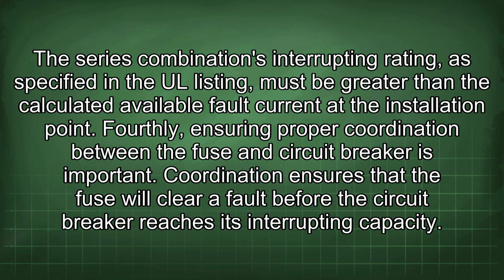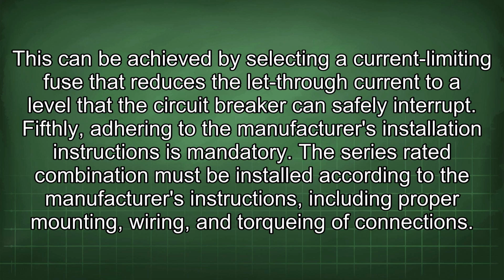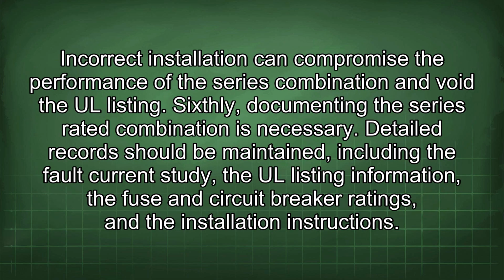Fourthly, ensuring proper coordination between the fuse and circuit breaker is important. Coordination ensures that the fuse will clear the fault before the circuit breaker reaches its interrupting capacity. This can be achieved by selecting a current-limiting fuse that reduces the let-through current to a level that the circuit breaker can safely interrupt. Fifthly, adhering to the manufacturer's installation instructions is mandatory. The series-rated combination must be installed according to the manufacturer's instructions, including proper mounting, wiring, and torquing of connections. Incorrect installation can compromise the performance of the series combination and void the UL listing.